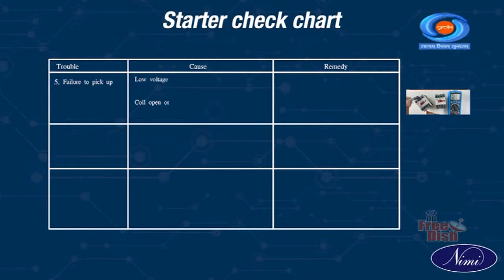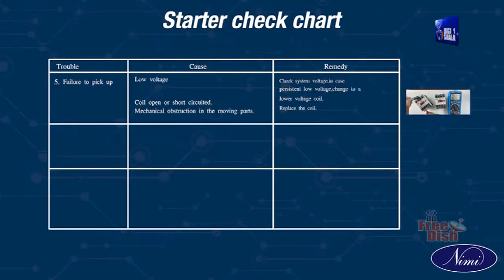Trouble. 5. Failure to pick up. Cause. Low voltage, coil open or short circuited, mechanical obstruction in the moving parts. Remedy. Check system voltage. In case of persistent low voltage, change to a lower voltage. Replace the coil. Clean and check for free movement of contact assembly.